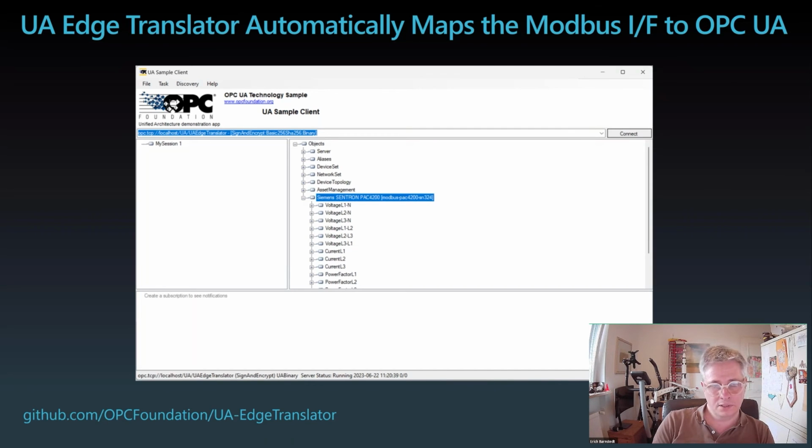One important part that some connectivity solutions already do, like, I know Softing dataFEED does it, is it would really help if your mapped assets in the industrial connectivity software end up in separate namespaces. So you have one OPC UA namespace in the OPC UA server's address space per configured asset, right? Because otherwise, I've seen implementations where you just get a flat list and all assets, doesn't matter where they come from, end up in that flat list. And then once you start connecting to it and trying to figure out which asset belongs to what, or which OPC UA telemetry tag belongs to which asset, it's a real pain. So it's better to put them into separate namespaces.